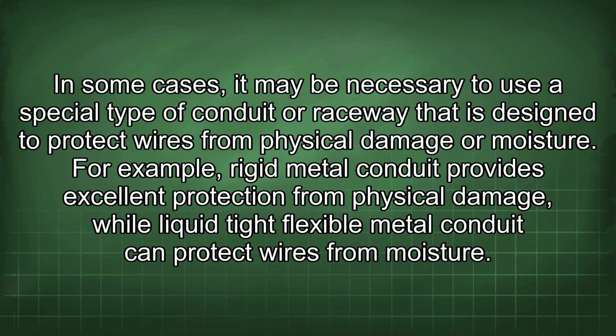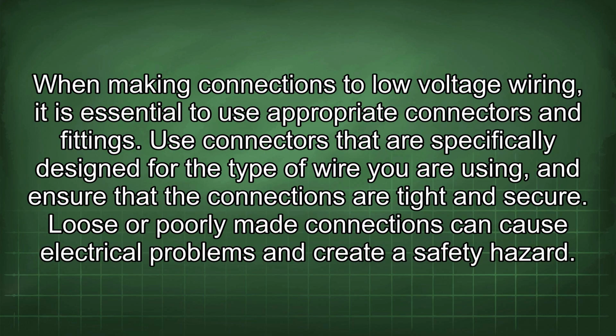In some cases, it may be necessary to use a special type of conduit or raceway that is designed to protect wires from physical damage or moisture. For example, rigid metal conduit provides excellent protection from physical damage, while liquid-tight flexible metal conduit can protect wires from moisture. When making connections to low-voltage wiring, it is essential to use appropriate connectors and fittings.